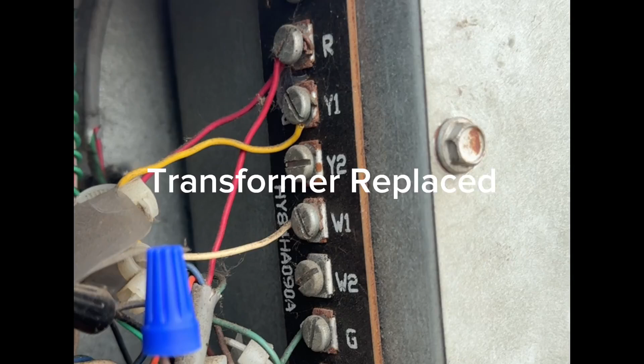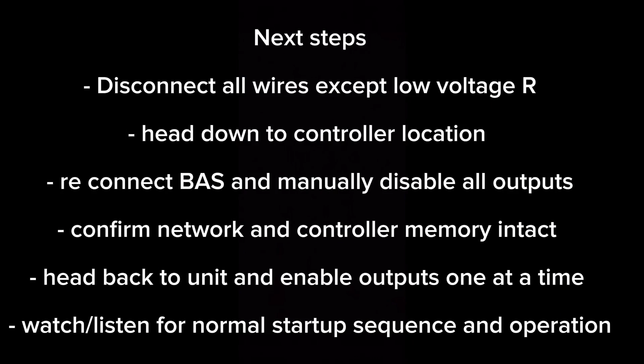After replacing the transformer, I came back and checked R with my meter, and I was in fact getting 24 volts AC. These were the next steps I did, and you can read along, but I just wanted to make sure nothing happens on startup.